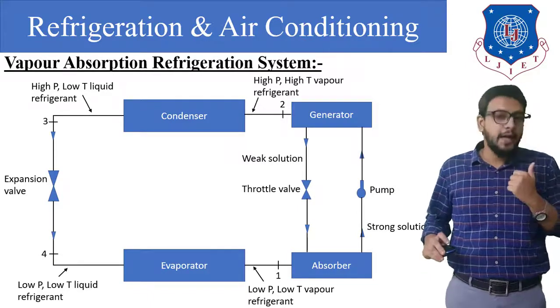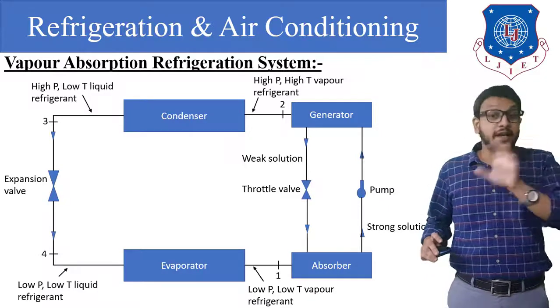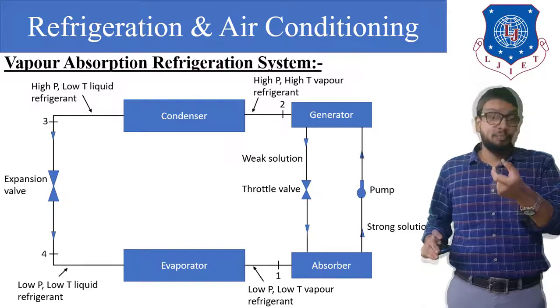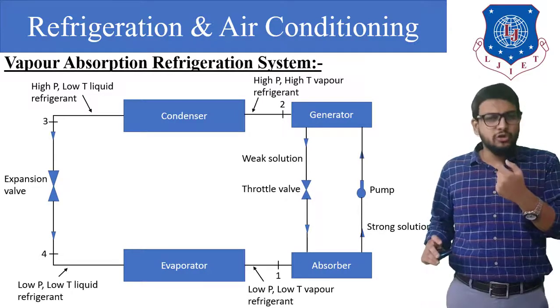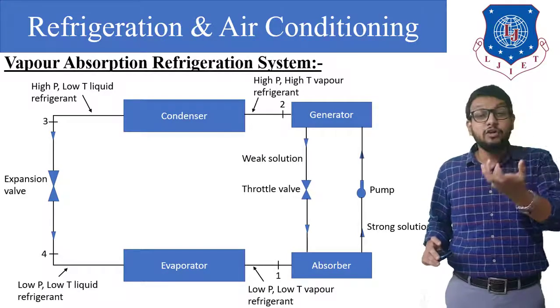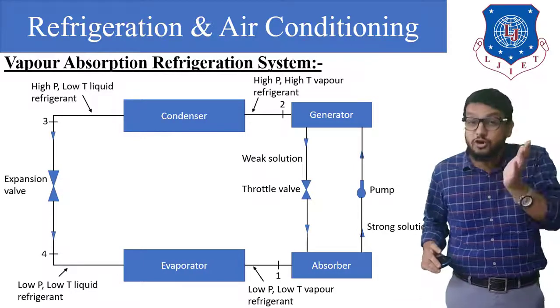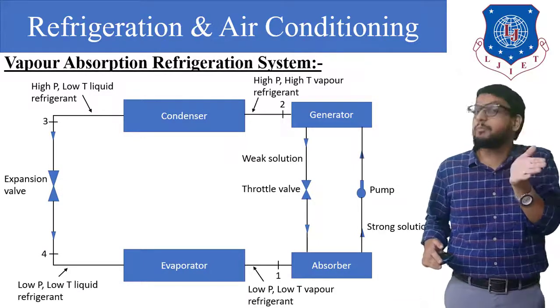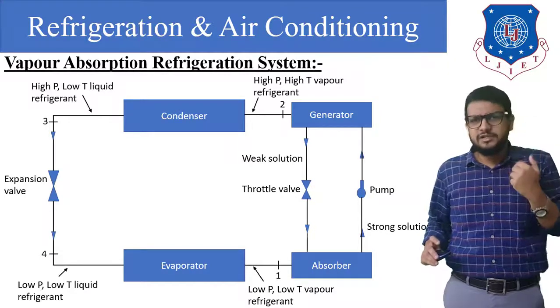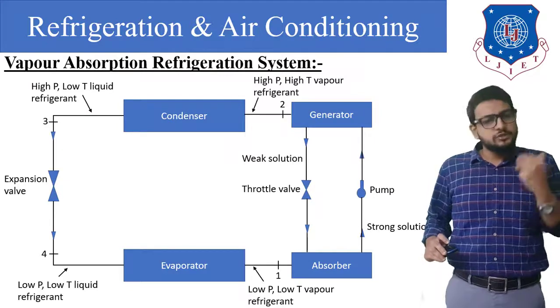The generator is not an electric generator. It is called a generator because heat energy is supplied to the strong solution of ammonia inside it. Because of that, ammonia's solubility decreases with increasing temperature, and vapor ammonia gets separated from the strong solution and enters the condenser. The throttle valve's function is to reduce the pressure of the weak solution flowing back from the generator into the absorber.